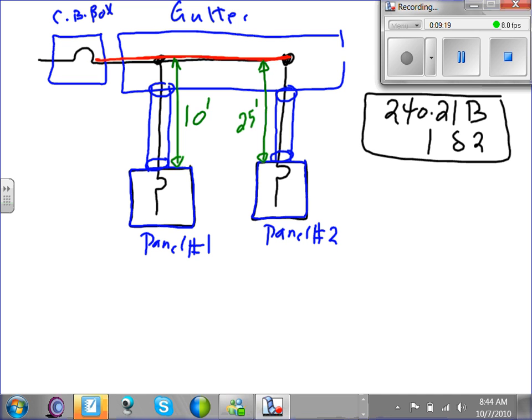Repeat, these are very important rules. For the 10 foot, you can look at it either way: the conductor amps cannot be less than 1/10 of the overcurrent device. For the 25 foot, the rule is the tap conductors cannot be less than 1/3 of the overcurrent device. Let's take an example. Makes it very clear when we take an example.